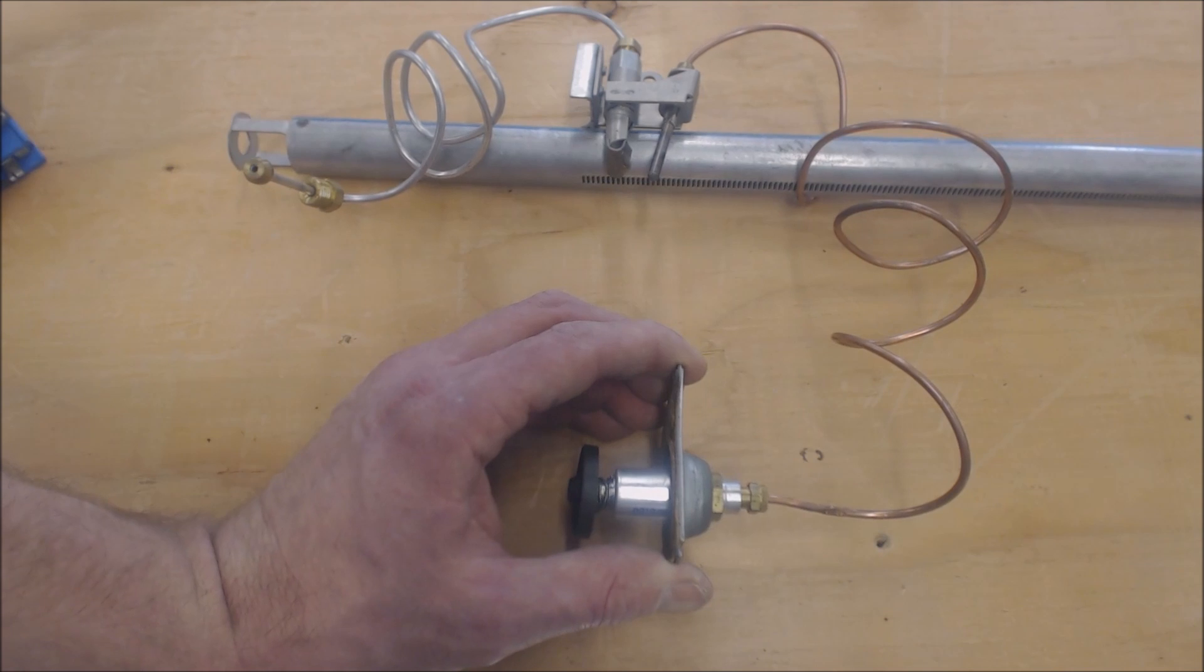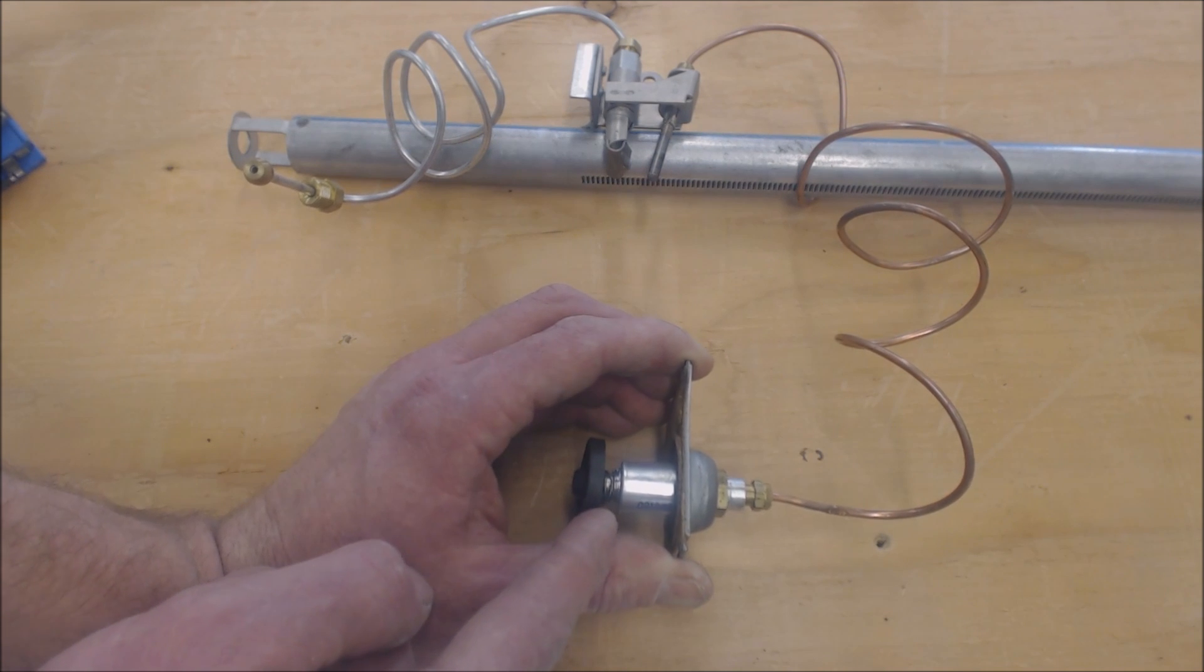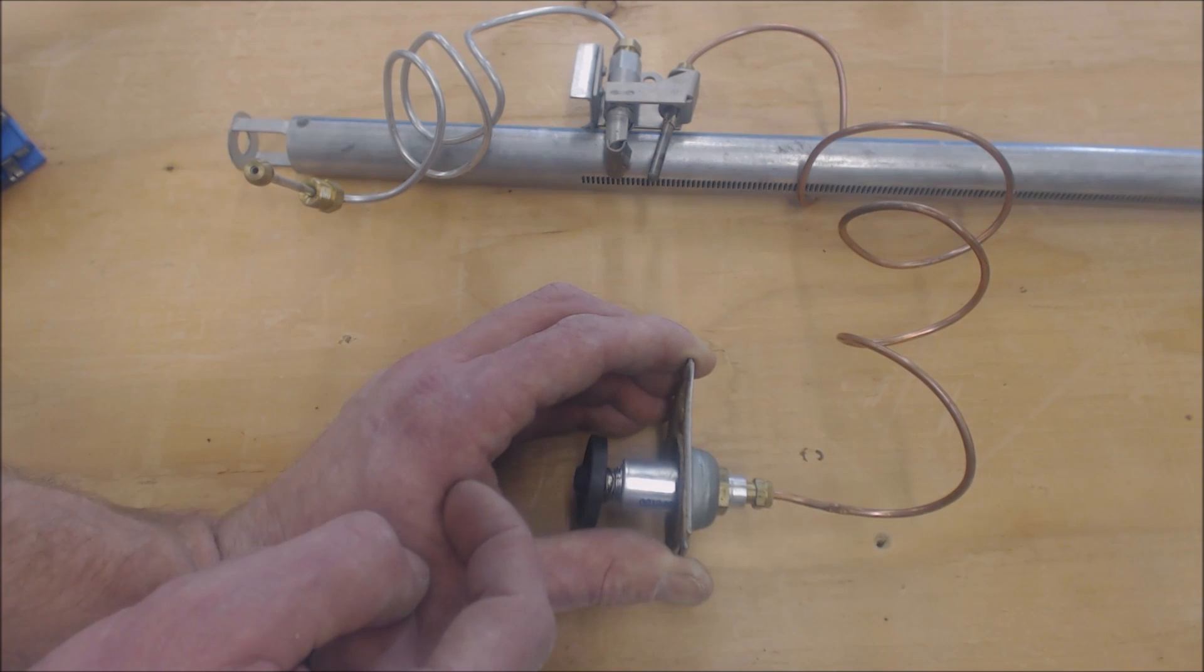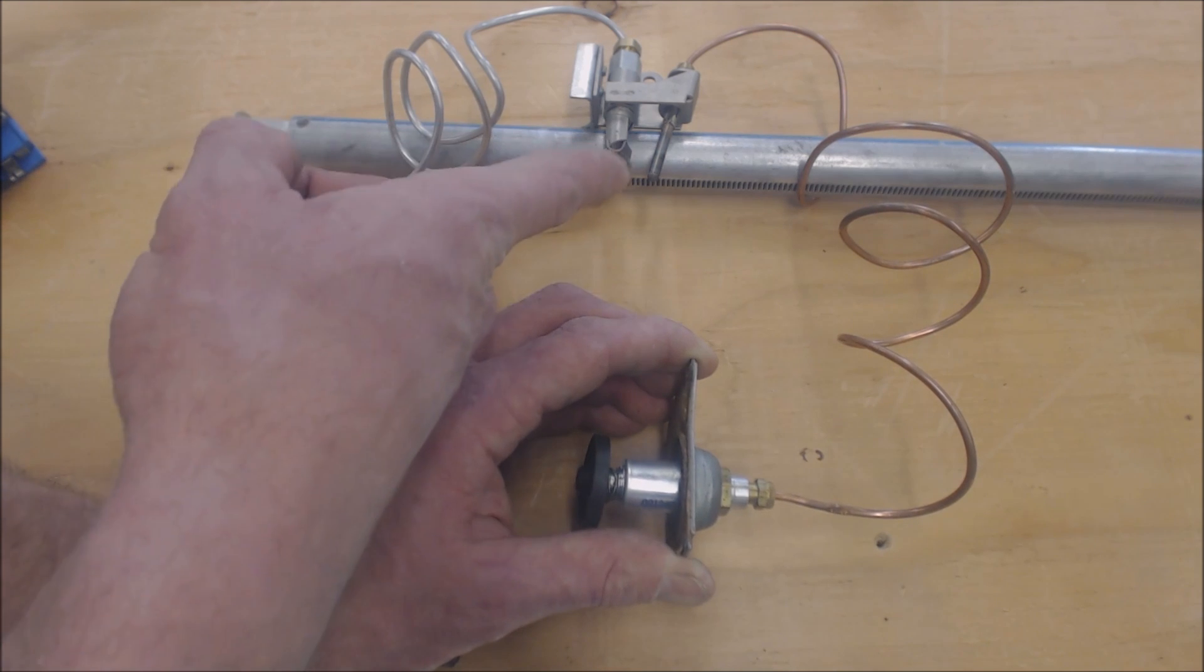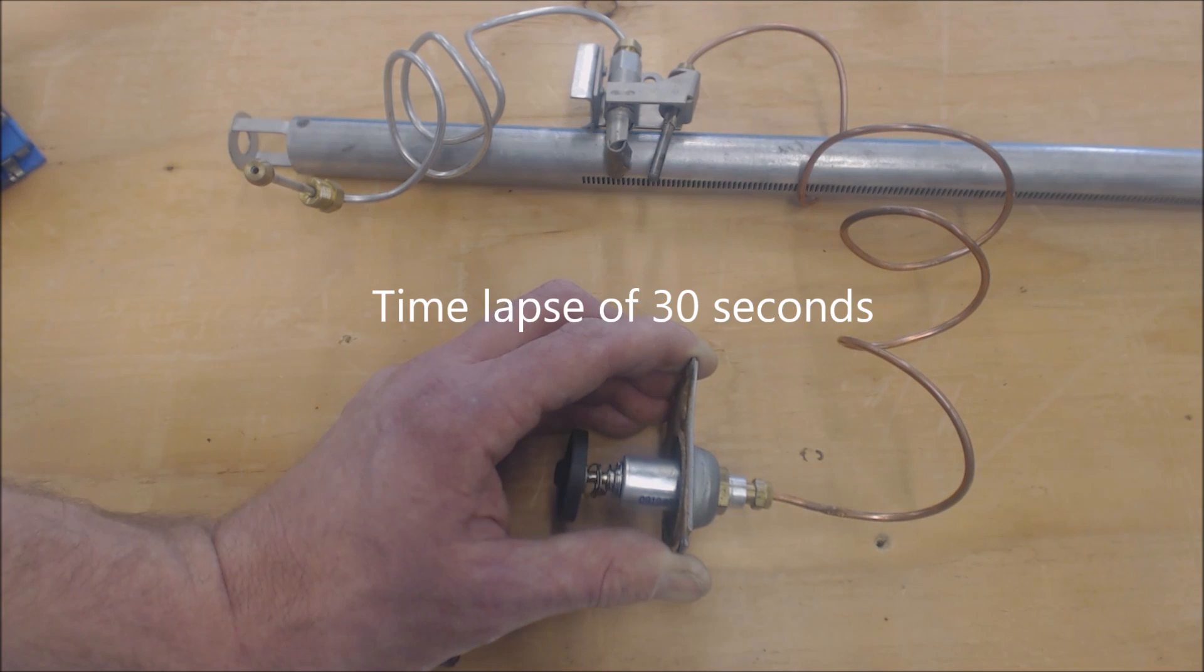You see that the solenoid is actually holding itself in. We're going to see that this will pop back open again once that thermocouple rod cools down. Now you see it popped open.